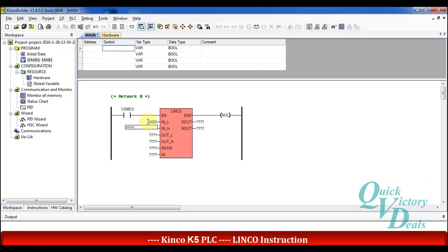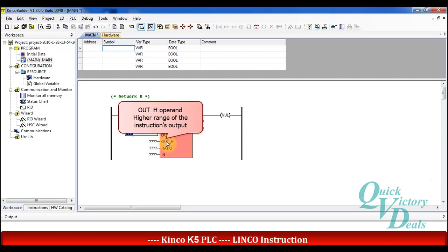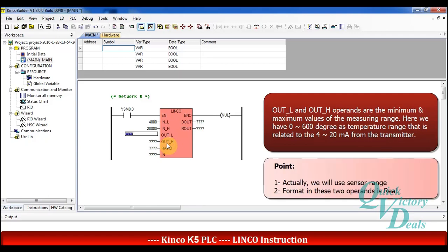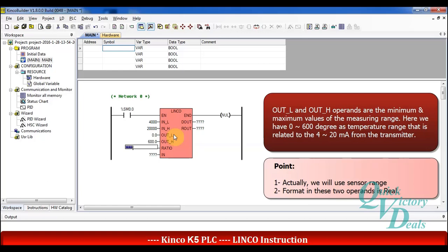The operands OUT_L and OUT_H represent the range we want to convert the current to — in this case, the range of the PT100 sensor. So OUT_L is equal to 0 and OUT_H is 600. Since these are real values for temperature, we should use real format for these values.